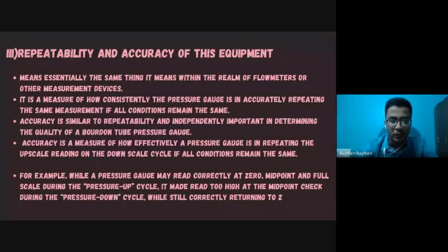Accuracy is a measure of how effectively a pressure gauge repeats the upscale reading on the downscale cycle if all conditions remain the same. For example, while a pressure gauge may read correctly at 0, midpoint, and full scale during the pressure up cycle, it may read too high at the midpoint check during the pressure down cycle, while still correctly returning to 0.